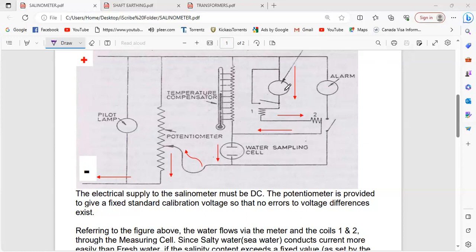Also, this acts as extra protection for the movement of this particular meter. But the prime reason this temperature compensator is used is so that you don't get unnecessary alarms. The extra current, due to the conductivity nature of your seawater from high temperature, will be bypassed through this. As the temperature rises, this particular resistance is going to be shorted out.